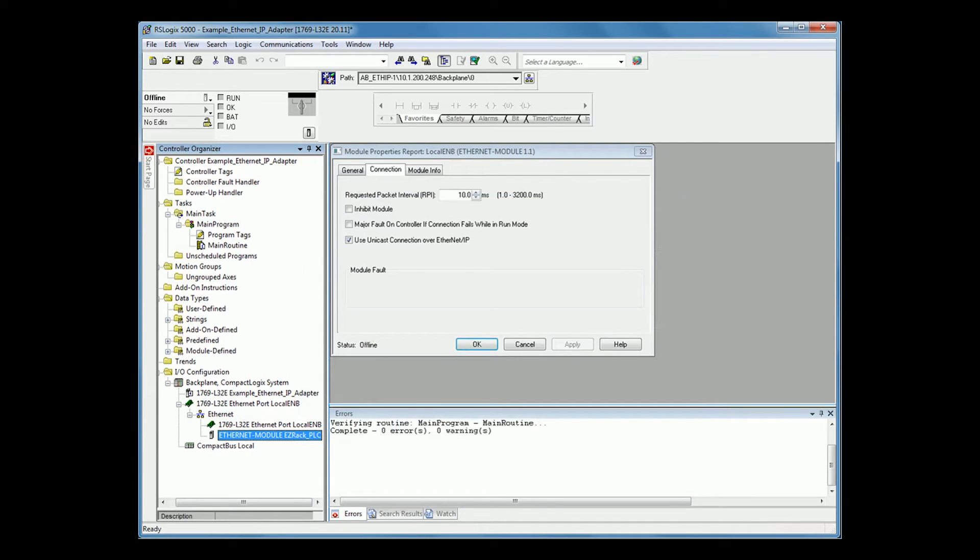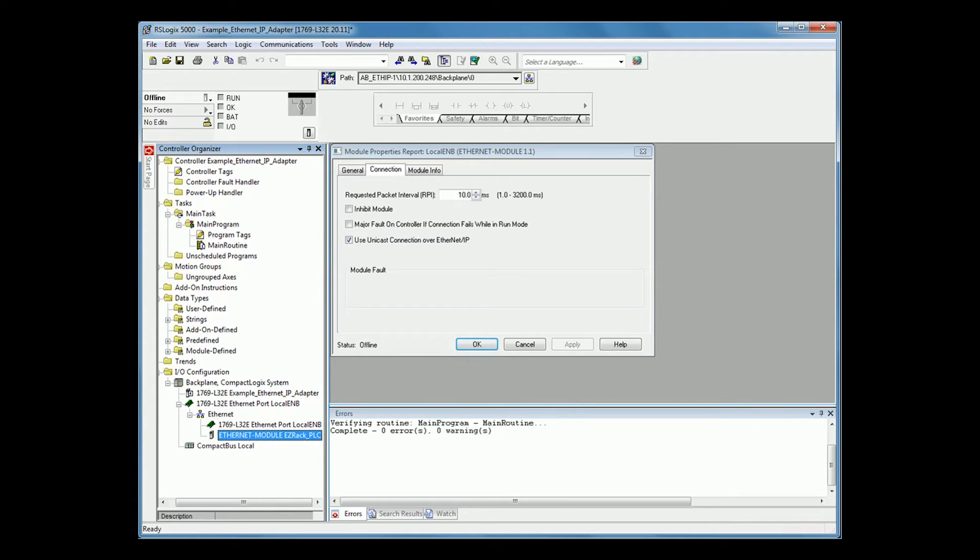Once you press OK, you have now set up your Ethernet IP adapter to scanner communication. Here, in your connection information, you can set up your request packet interval. 10 milliseconds is fine for my communication. Please set it up to whatever is the slowest speed you can tolerate.